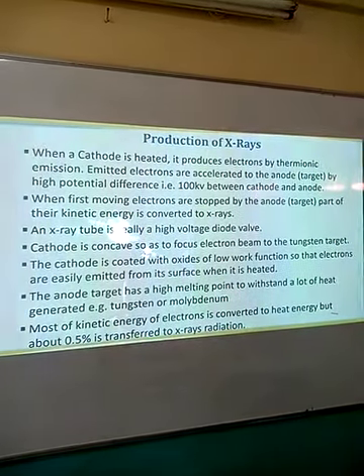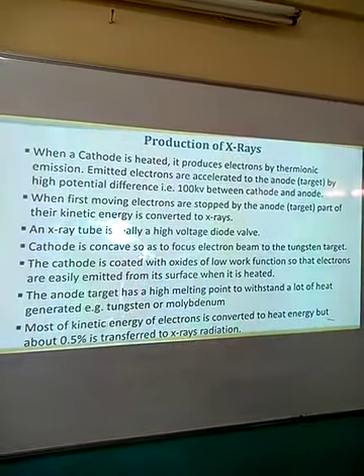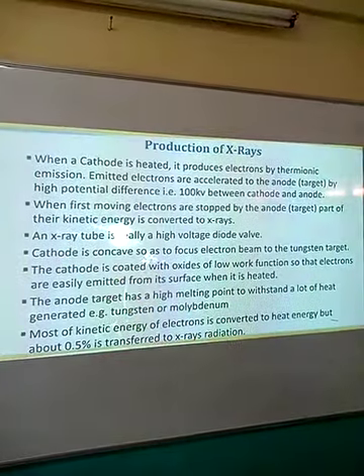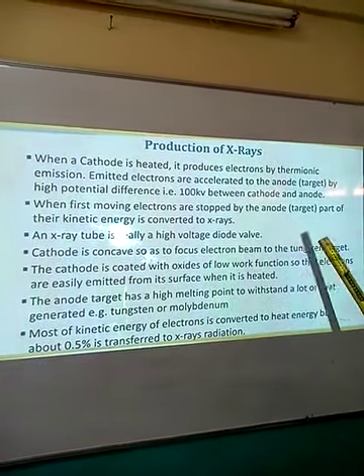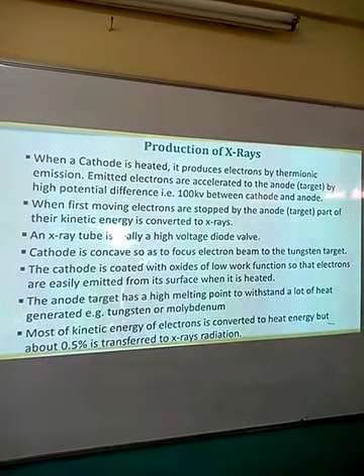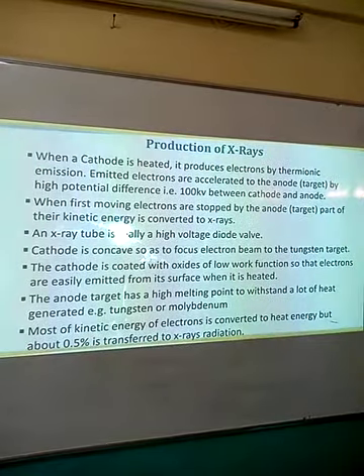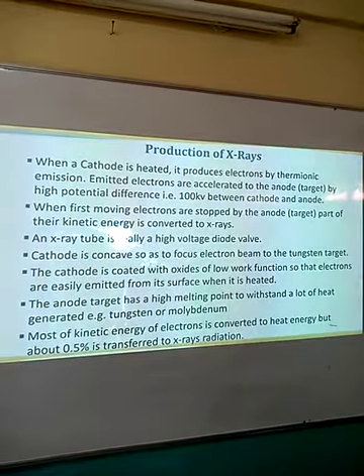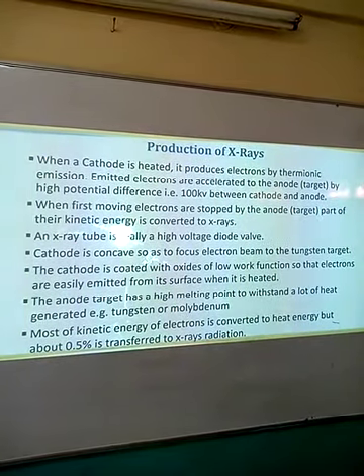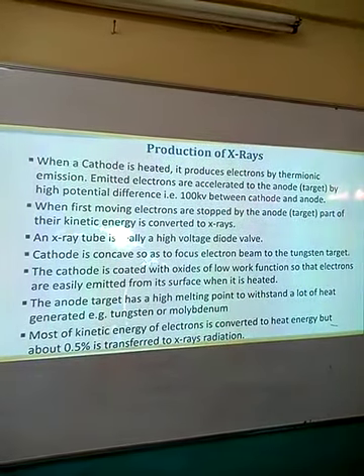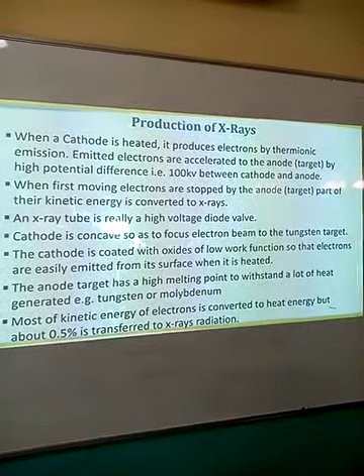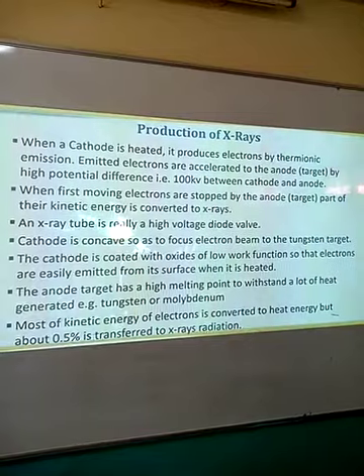The X-ray tube operates at a very high voltage. This enables the production of electrons at the cathode. The cathode is concave in shape, which is meant to focus the electrons to the target. The cathode is coated with oxides of low work function. The purpose of that is to enable the emission of electrons from the surface of the heated cathode. The anode target has a high melting point, to withstand the large amount of heat generated at the point of impact. Examples of target materials are tungsten and molybdenum. Most of the energy of the electrons is converted into heat, but 0.5% is used to produce the X-rays.